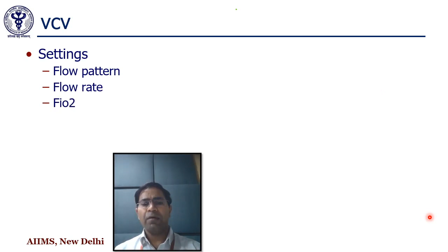Inspiratory trigger is around 2, whether it is pressure or flow, we keep it around 2. If you talk about the tidal volume, it depends upon the predicted body weight of the patient and compliance of the patient, or compliance of the lung more appropriately. Usually the compliance is around 40 to 50 in an intubated adult. If the compliance is good, maybe 50, then we can give a tidal volume around 8, maybe 9. If the compliance is poor, we start from 6 ml per kg.